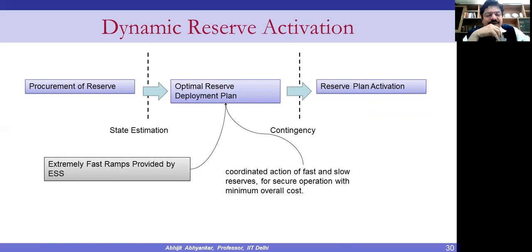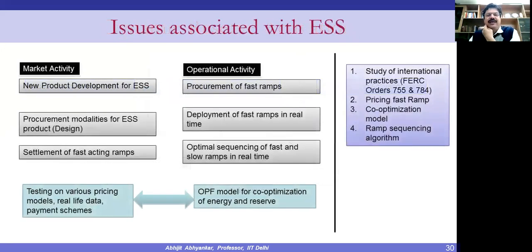Extremely fast ramps provided by ESS are of course considered, and there's a coordinated action of fast and slow reserves. Immediately after a fault or contingency takes place, the fast ramps come into picture immediately, and those are replaced by slow ramp units later on. So there's an optimization that takes place which has technical as well as commercial aspects, and those get embedded into the optimization carried out.